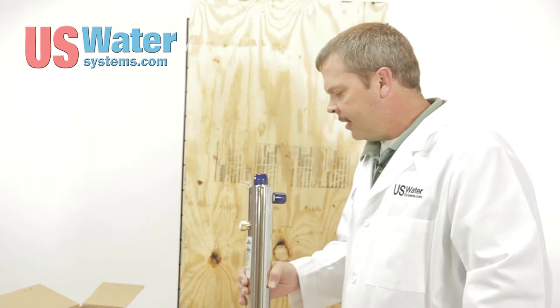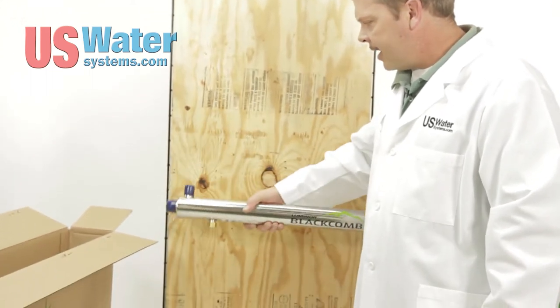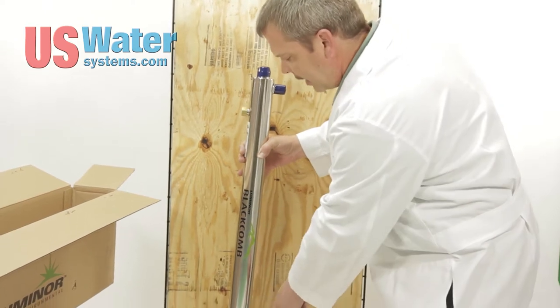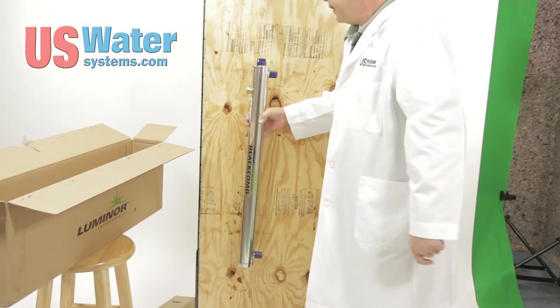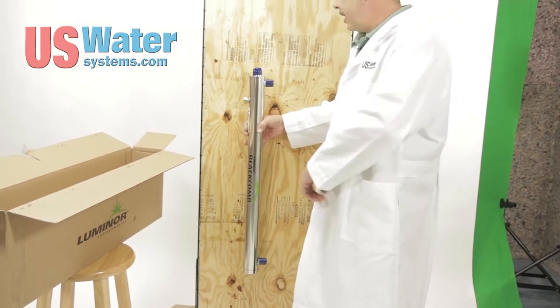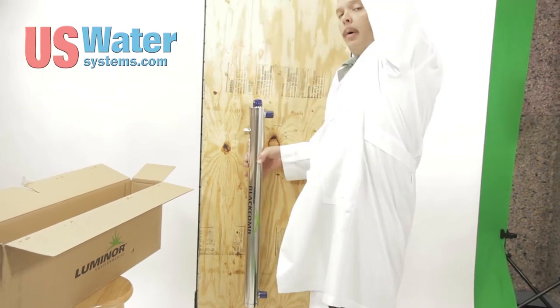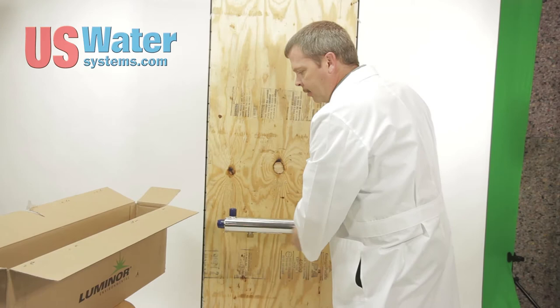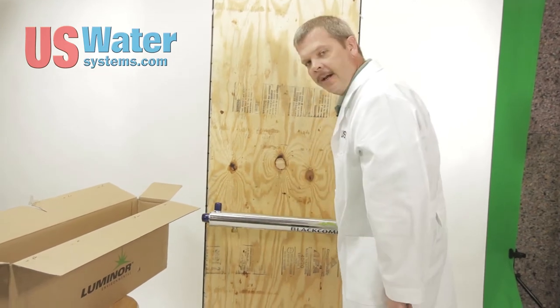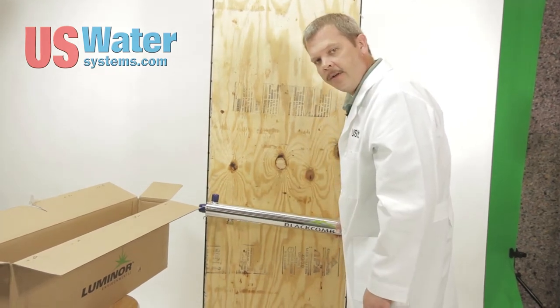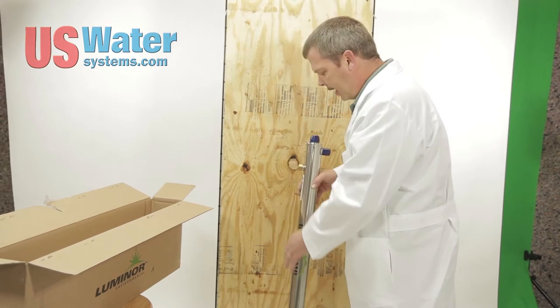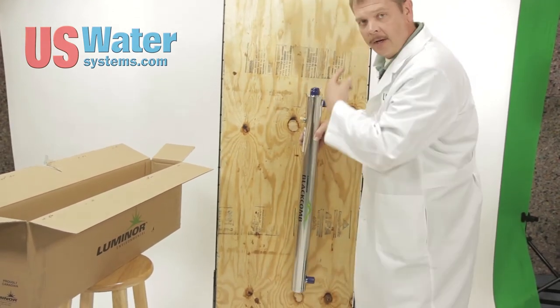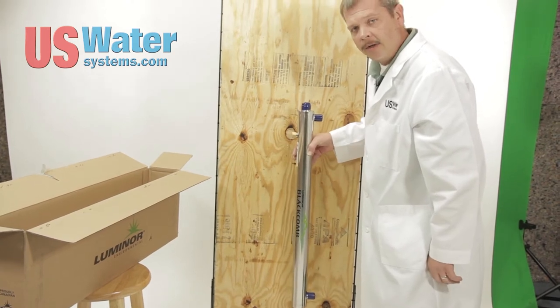These UVs can be mounted vertically or horizontally. We like to mount them vertically and come in from the bottom and go out from the top. When you do this, you have to make sure you have adequate clearance to pull the bulb out when it's time to change the bulb. You don't want to put this backed up into a corner where you can't get the bulb out and you have to remove the system every time. You basically want the same amount of clearance as the length of your UV so you have plenty of room to get the bulb out when it's time for a change.